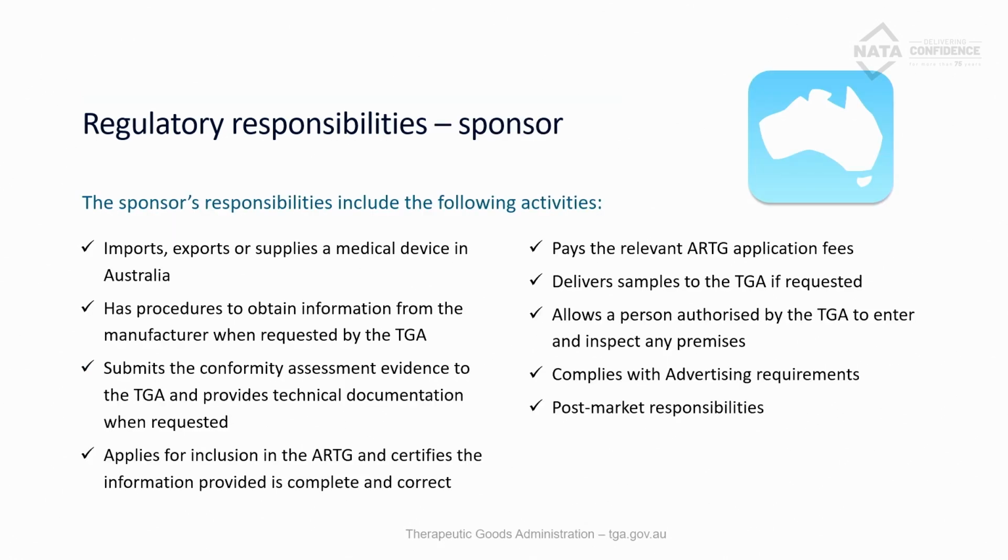And I'm going to scoot through some of these so that we've got time for questions at the end. So up here you've got the responsibilities of a sponsor. And from a laboratory perspective, many of these responsibilities are not relevant to an in-house IVD manufacturer who also happens to be a sponsor, because in-house IVDs are exempt from inclusion in the ARTG. So you don't have to submit that application, but bear in mind that you still do have to submit that notification that you are a laboratory with in-house IVDs and you're the manufacturer.